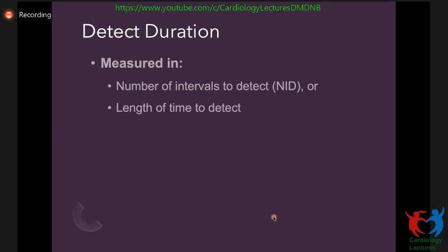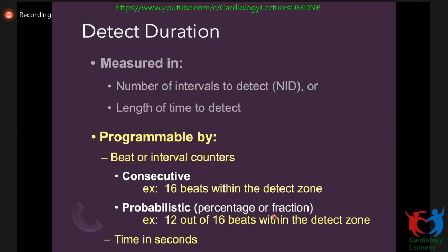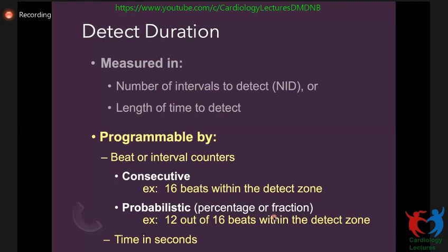The detection count can be programmed as consecutive beats — for example, 16 fast beats in a row — which then meets the detection criteria for VT or VF. Alternatively, it can be probabilistic: for instance, if 12 out of 16 beats meet the fast rate criteria, the device classifies it as VT or VF. You can program ratios such as 8 of 10, 12 of 16, or 10 of 20, depending on what you set.